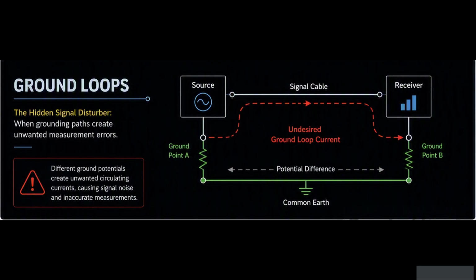In addition to shielding, another important concept in signal integrity is the ground loop. A ground loop occurs when a potential difference, or voltage difference, exists between two grounding points in a system. Although both points are connected to ground, they may not actually be at exactly the same electrical potential. As shown here, the magnitude of this potential difference depends on factors such as the distance between the signal source and the amplifier, as well as the ground resistance at both locations. When equipment is connected through multiple grounding paths, unwanted current can flow through the signal circuit. This unwanted current can create electrical noise, distort measurements, and affect the accuracy of instrumentation signals.